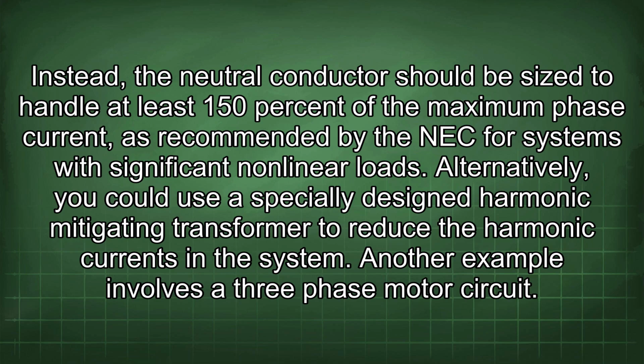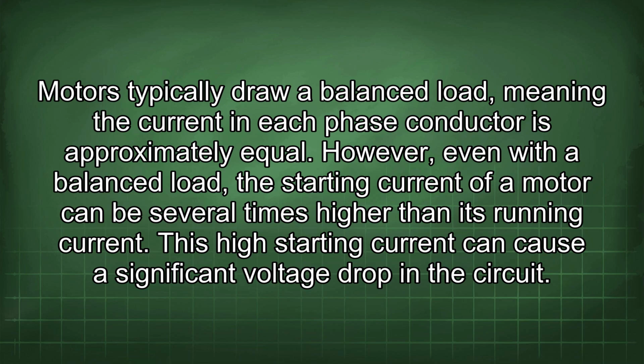Another example involves a 3-phase motor circuit. Motors typically draw a balanced load, meaning the current in each phase conductor is approximately equal. However, even with a balanced load, the starting current of a motor can be several times higher than its running current. This high starting current can cause a significant voltage drop in the circuit.